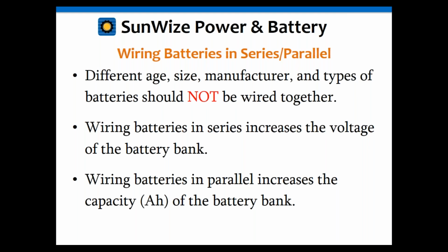You do not want to mix batteries of different age, size, manufacturers, and types, ever. I'll probably mention examples of what not to do. When that happens, the batteries just don't share the current correctly. They have different internal resistances, especially batteries of different age, because as batteries get older, the impedance inside them can change. Since these batteries have different resistance or impedance internally, they won't share current correctly, and one string or battery will get used more than the other, causing the entire battery bank to fail prematurely. So it's just something you don't ever want to do—it'll cost more money and cause damage to perfectly good batteries down the road.